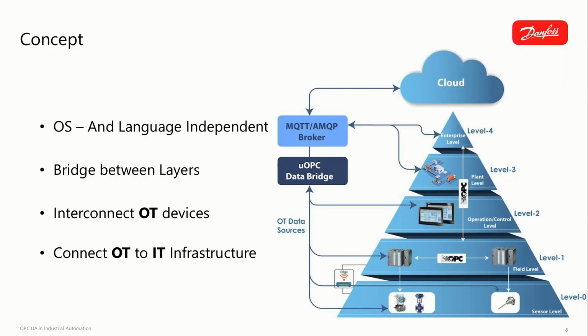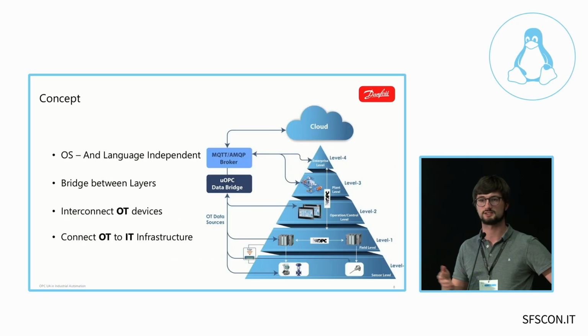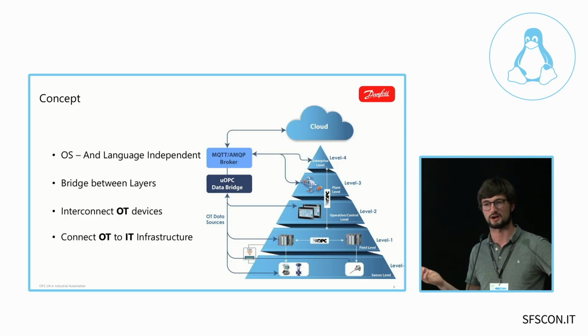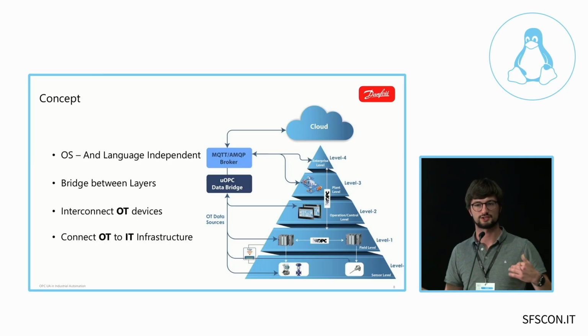More importantly, it is basically OS and also language independent. The old specifications, the OPC specifications, were pretty Microsoft heavy, and they moved away from that completely with OPC UA, and now it's basically completely operating system and language agnostic. We did the workshop, we had Linux, Windows, and microcomputers there, and they all were able to communicate with the drives or with the PLC, so that's quite nice. OPC UA is basically then just a bridge between a few layers.